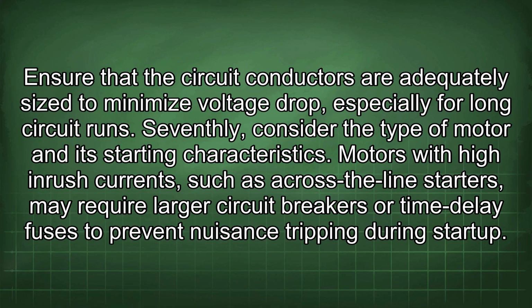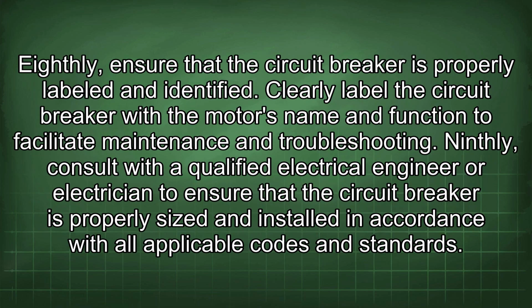Seventhly, consider the type of motor and its starting characteristics. Motors with high inrush currents, such as across-the-line starters, may require larger circuit breakers or time delay fuses to prevent nuisance tripping during startup. Eighthly, ensure that the circuit breaker is properly labeled and identified. Clearly label the circuit breaker with the motor's name and function to facilitate maintenance and troubleshooting. Ninthly, consult with a qualified electrical engineer or electrician to ensure that the circuit breaker is properly sized and installed in accordance with all applicable codes and standards.